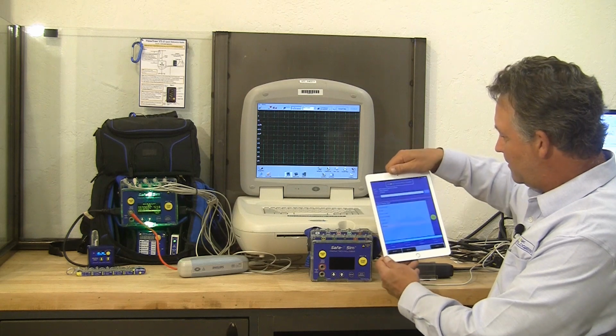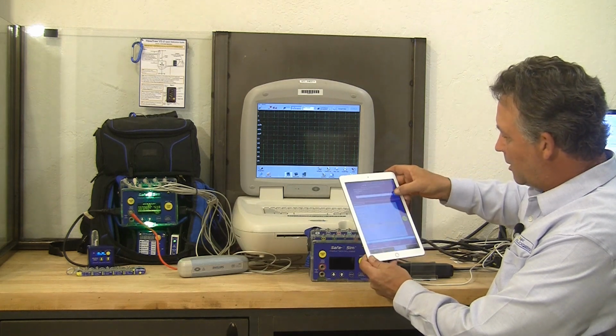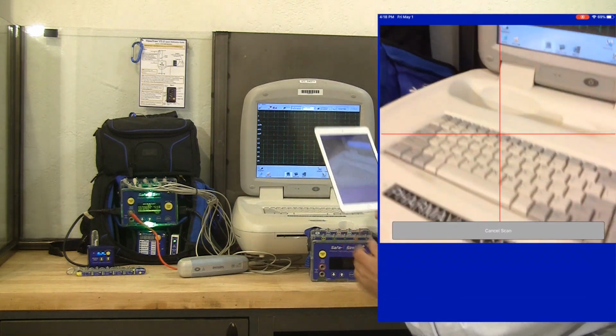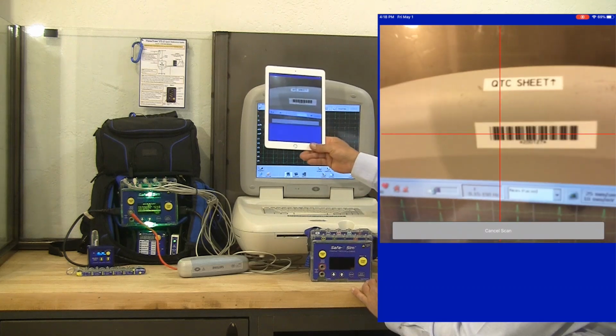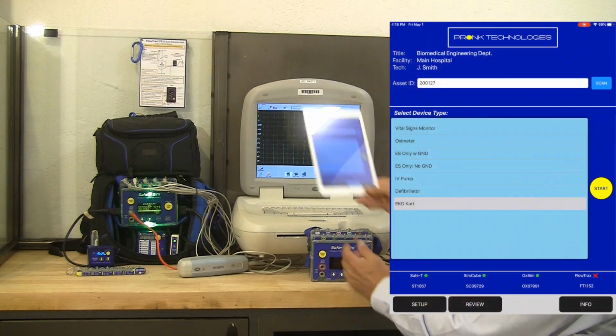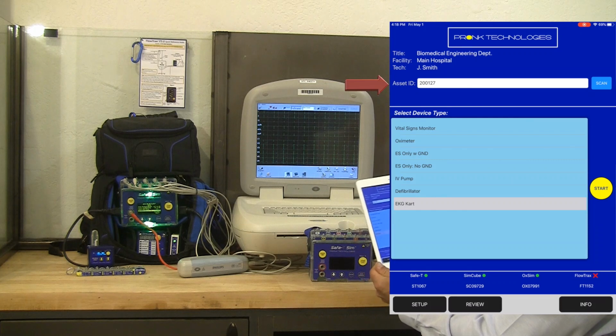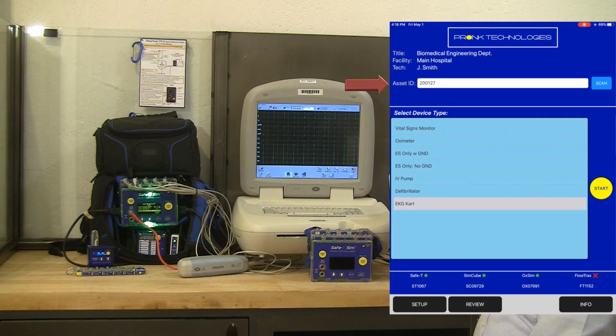So we're going to take the iPad, we're going to do a barcode scan to start with of the device we're about to test. That'll give us the asset ID throughout our testing so that at the end we've got an electronic record that has all the detail we need. So from the asset ID scan, we've got that, and then it's just a matter of selecting the device type. I've got EKG cart selected. I'm going to hit start.